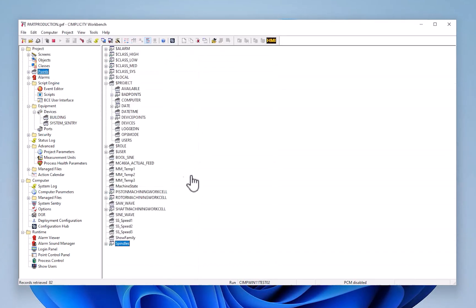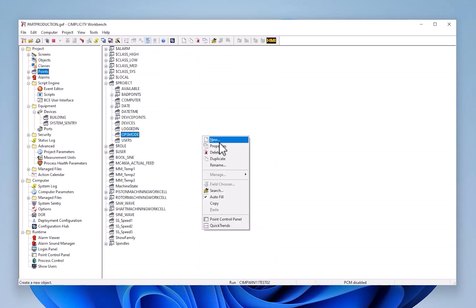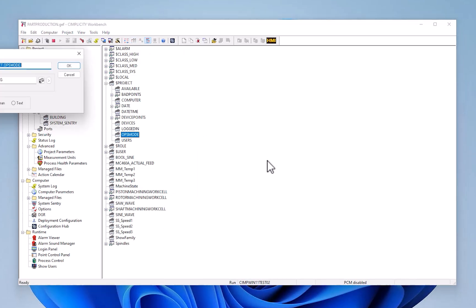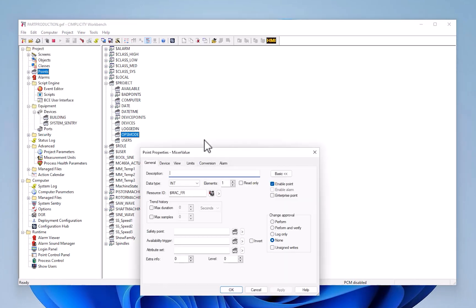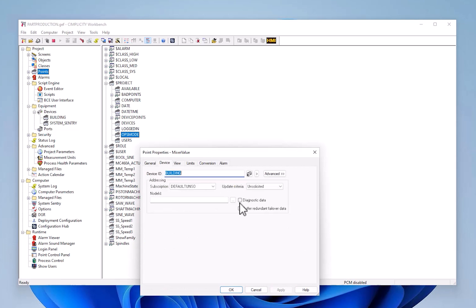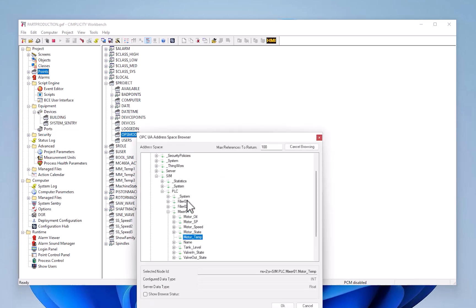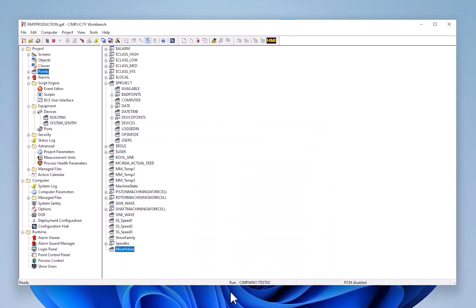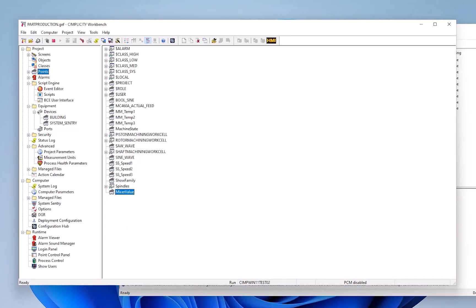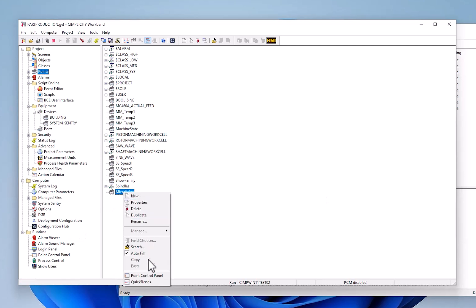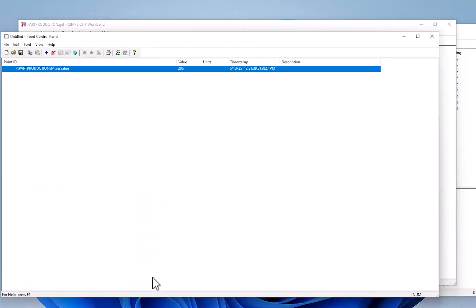If I go to my points database, I can create a new point to retrieve a mixer value from that OPC UA server that is monitoring a mixer. We allow you to browse for those measurements. For example, if I wanted to retrieve the motor temperature of Mixer One, I can go ahead and do that. Once you've created that point, you can take a quick look at its value using the point control panel.